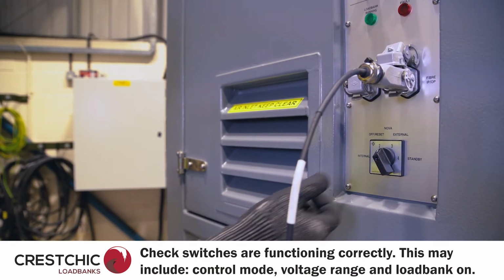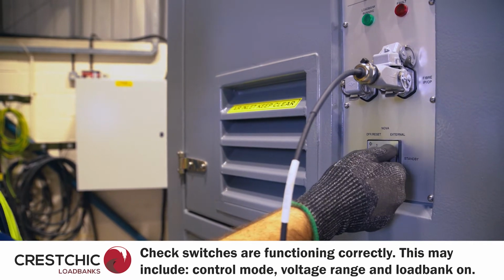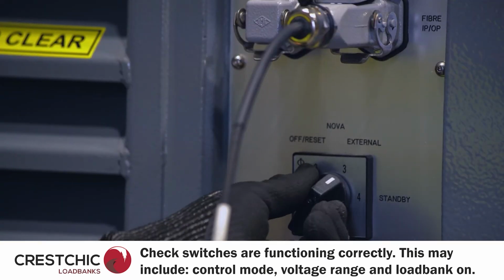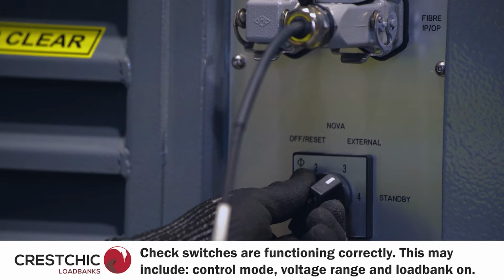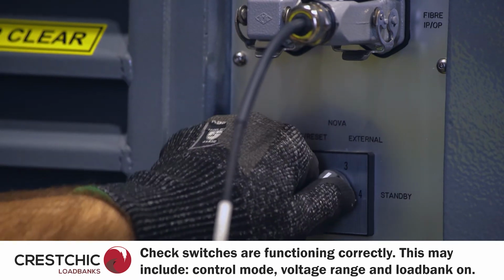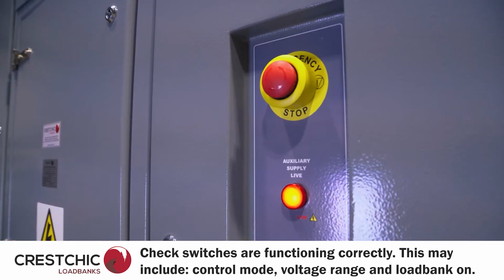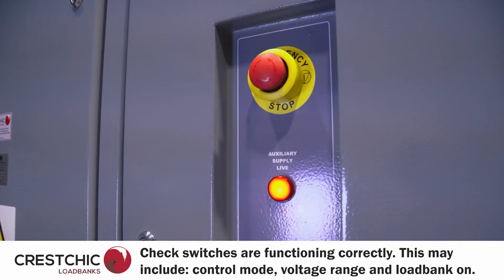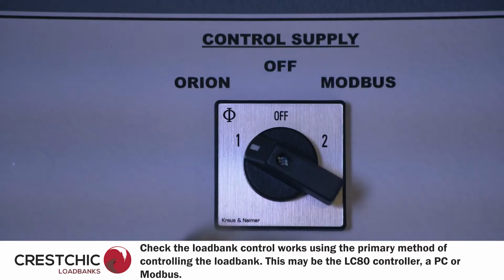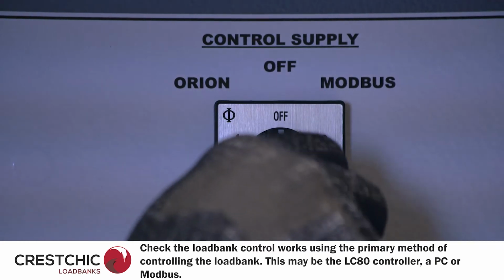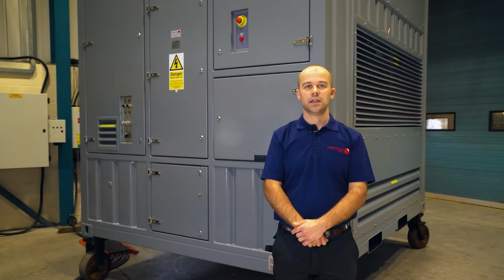Check control switches are functioning when switched to the required positions. For example, switching the load bank control switch from off to external will allow power to the majority of the control circuit. Don't forget to check the emergency stop is out. Once the control switches are in the correct positions, communication with the load bank controller can be established. Please refer to the Orion software manual on using this software.